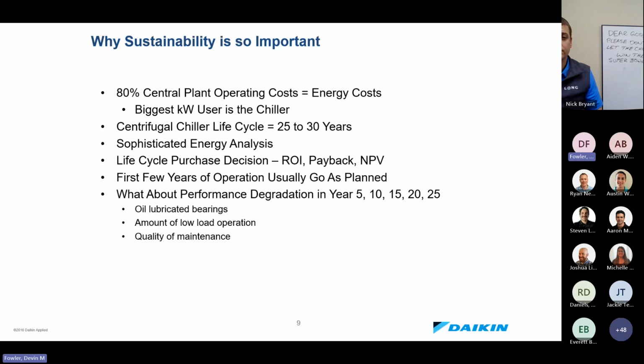During normal operation, in your first few years of running that chiller, you're going to get the efficiencies and the loads that you would typically see in your ratings. But your performance is going to degrade with an oil chiller, especially within the first 5 to 10 years, and even more so as we get into 15, 20 years into the life of that chiller. A big reason for this is the oil lubricated bearings. One, you're going to have wear on the bearings. Two, you're going to have oil contamination and degradation in your system. You really need to look at the amount of time you're going to be at low load operation with that oil degradation in your system, because at lower loads heat exchange is very important, as well as your quality of maintenance.